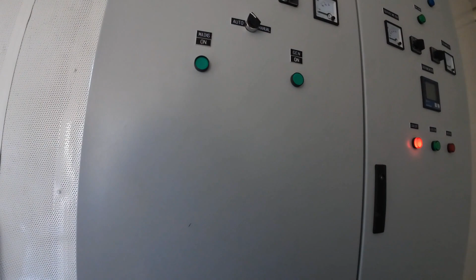In manual, and we'll try to make auto for everything. So we'll try to turn off the mains - if it automatically runs the generator and closes the breaker to the generator, then we will turn on the main supply, and it will transfer to the main supply and then automatically cool down the generator. So meaning to say it is working correctly. So let's try that.